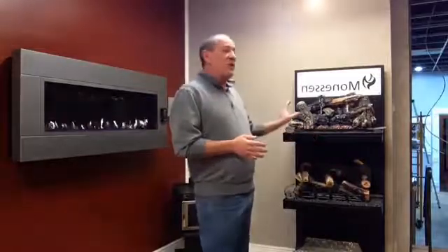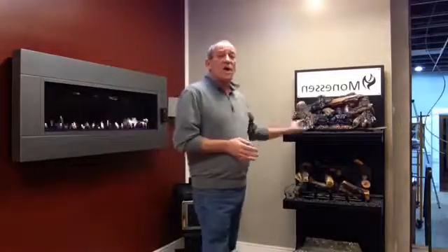When you're burning a vent-free appliance, it's burning up the oxygen in your home. Newer homes today are so well insulated that you can't get what's called makeup air into the home. And this is true on most anything you have in your home. You've got to make sure that makeup air is coming into your house or you're going to live inside of a giant igloo cooler because of all the foam insulation that they put in the houses today. So if we were to install that vent-free appliance in your home, we would have to open up a large hole for air to come in to help make up for the oxygen being depleted out of your home.